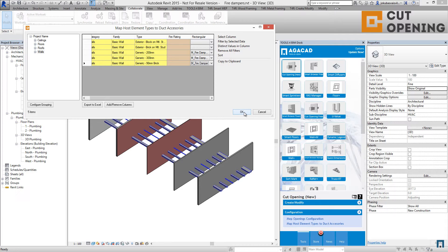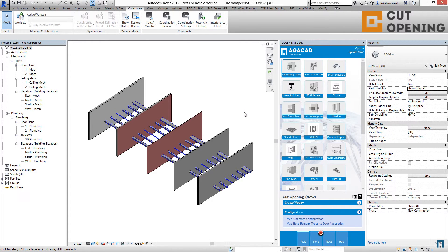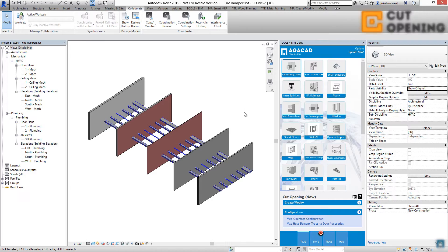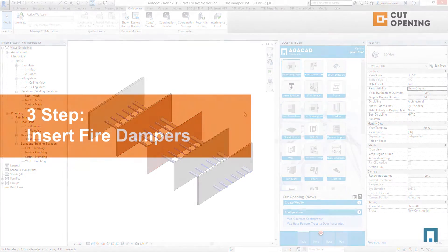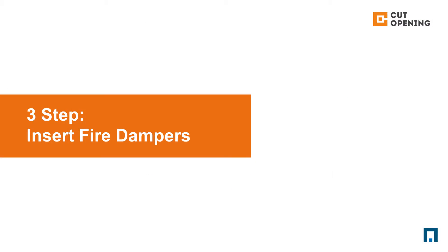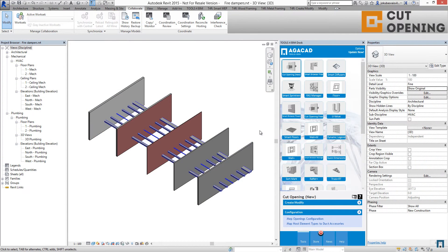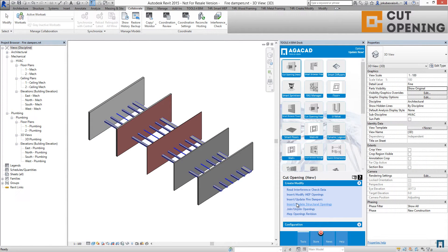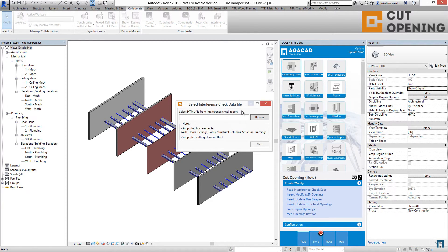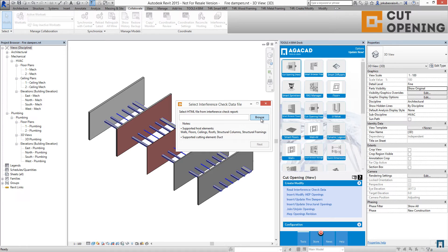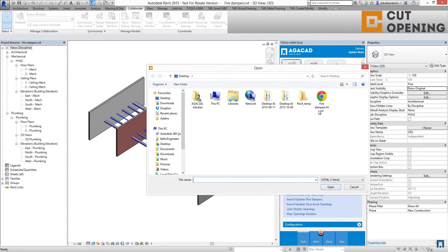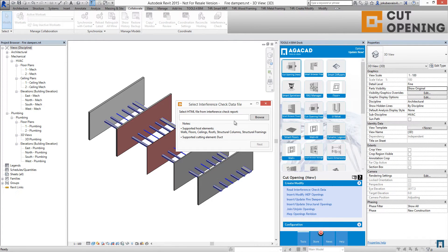I'm clicking OK, and now I mapped all the walls with ducts to know the places where the fire dampers should be inserted. The next step, you should go to the create modify tab and use insert update fire dampers. You should read the HTML file that you saved before from Revit. You will get a report about that.